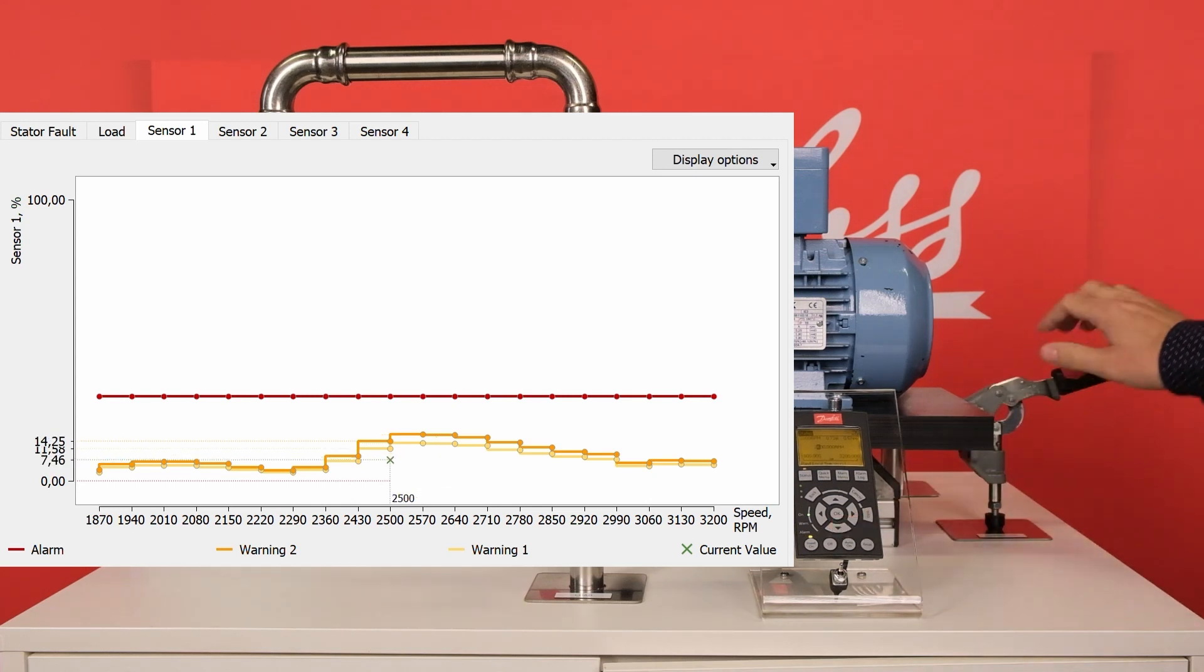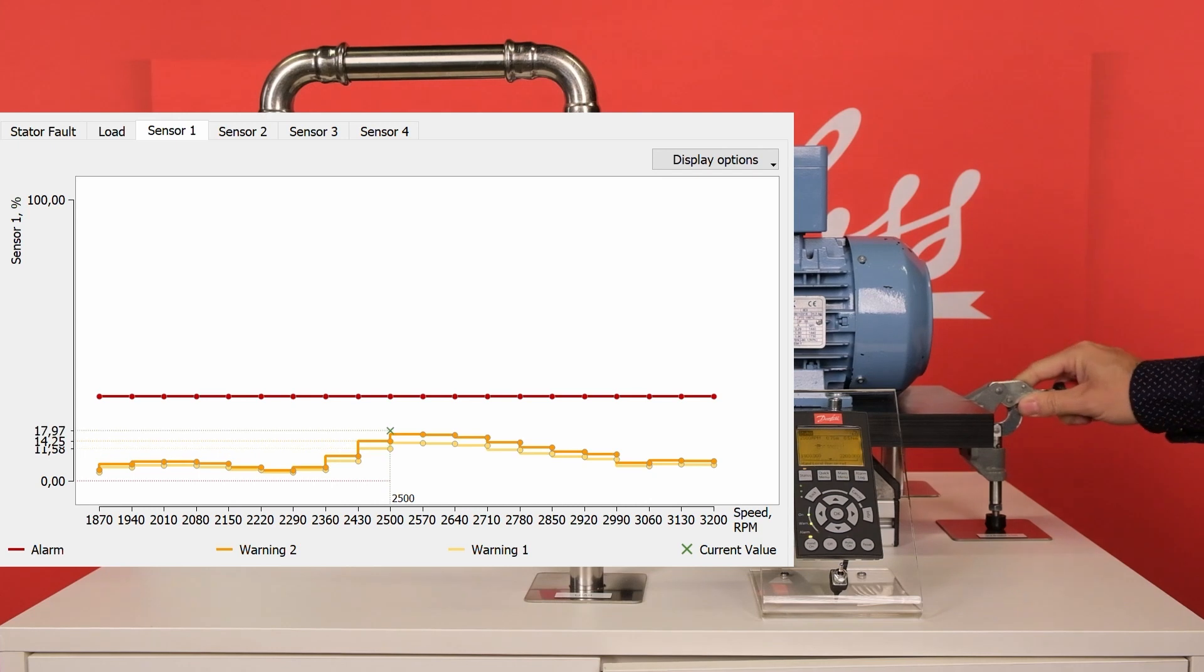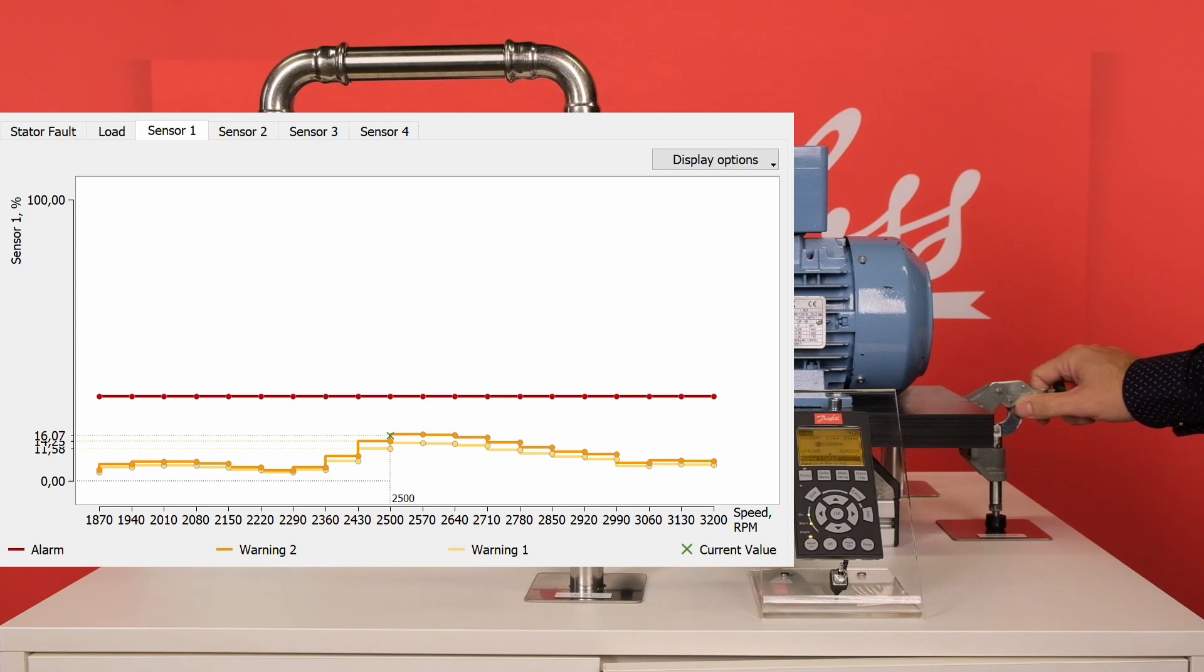You will have different vibration thresholds at different speeds, depending on the baseline measurement. This is also useful to find resonances which occur in some applications.